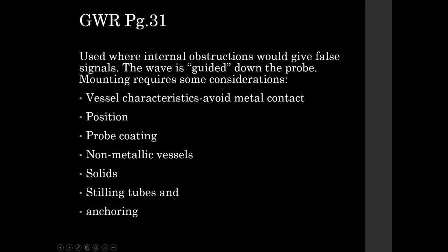Okay, guided wave radar, again, continuing here. These are generally used where internal obstructions would give false signals. The wave is guided down the probe, and this is how we get around it wanting to bounce all the way to the sides of the vessel. This guides it specifically to avoid any of those obstructions.